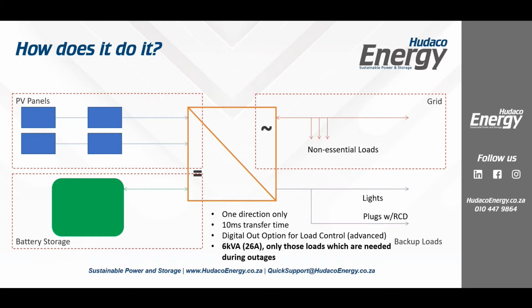And the main reason for that is nothing to do with here, nothing to do with the inverter. This part is very cheap. It's because they don't want to provide the battery power and the PV power to carry those loads. If you're going to run 10 or 8 kVA loads for 4 hours, you're going to need a huge battery stack, right? Of course, we can parallel a couple of these to allow for that. But in most of our cases, our clients aren't pulling more than 3 kVA during outages.